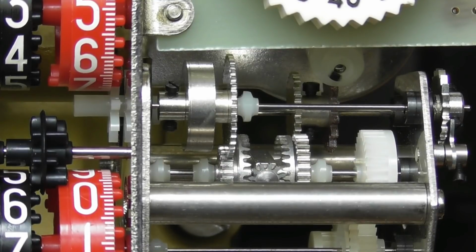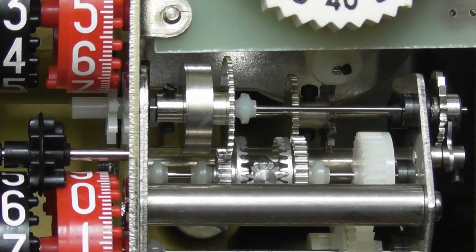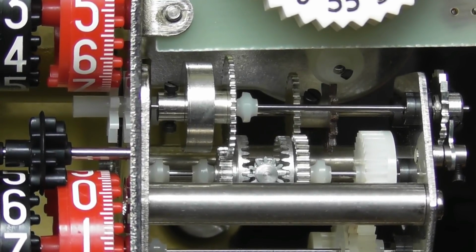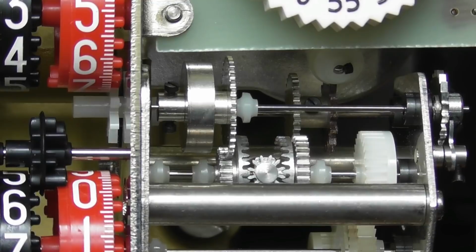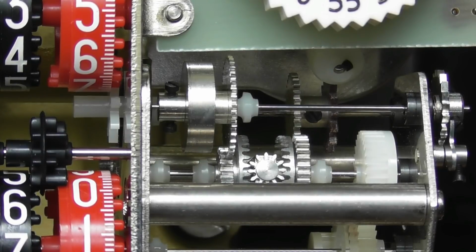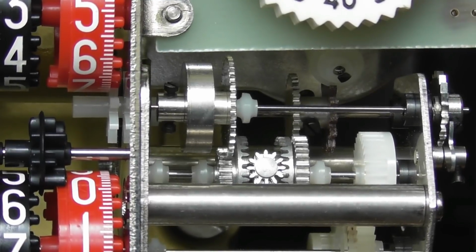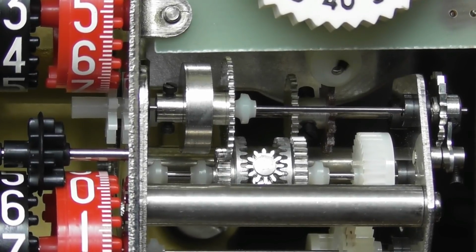So it is set up on a timing device which drives one part of the differential. That's the right hand gear set here, as I understand it. I'll put it up to 6 so it goes a bit faster. Yeah, it's pulsing away, it goes pretty fast. And then it has to match the meter speed. So if the meter speed is the same, there won't be any excess demand charged. If the meter speed is slower, there won't be any excess demand charged. But if the meter speed is over the set limit by means of this adjuster, which can be preset by the utility, then the extra electricity will be charged to the top register, at a special rate. So I've never seen this type of arrangement.